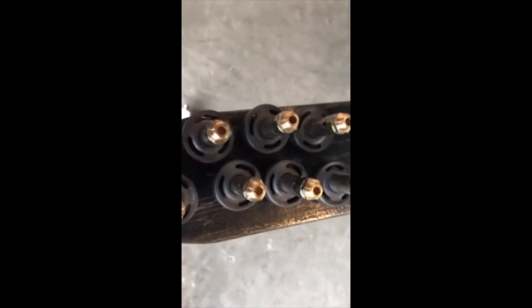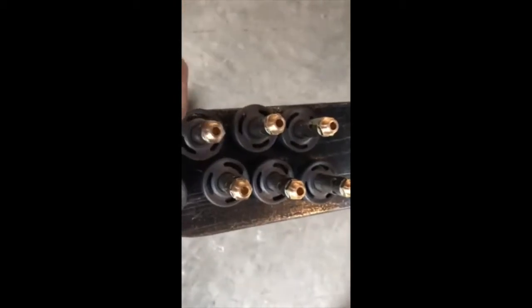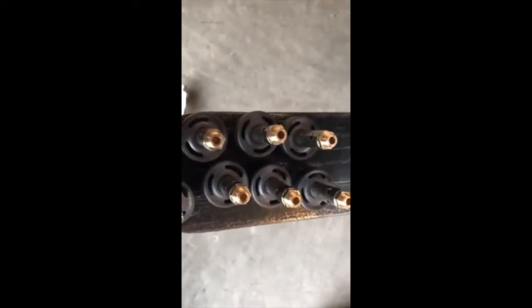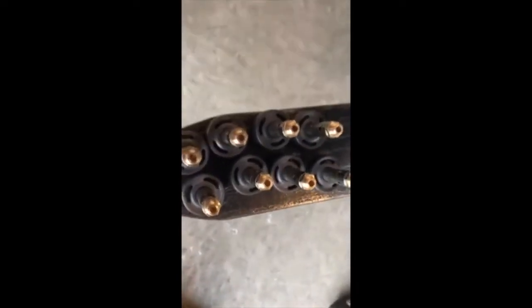We've replaced all the injector orifices — we're converting this to natural gas — and we've hand-tightened them in. Next, you put a sealant on the thread; make sure you don't get any blocking the entryway. What we like to use is the red RTV high temperature gasket maker, which is good up to about 600 degrees. What I really like about this sealant is it never hardens — it becomes rubbery — so it works perfect for this application.